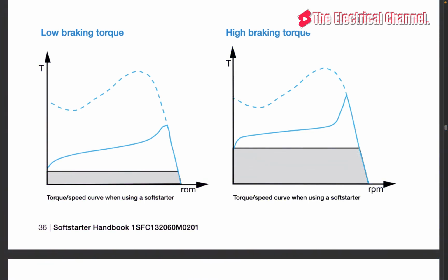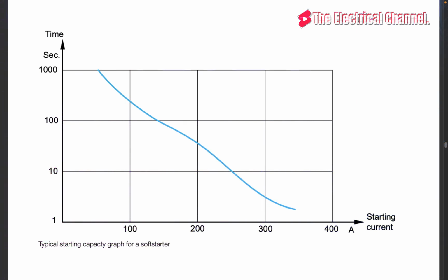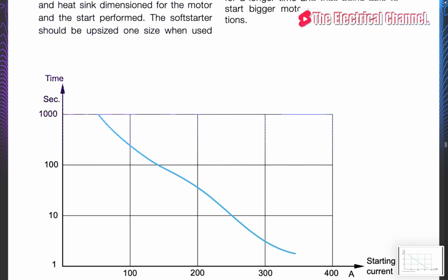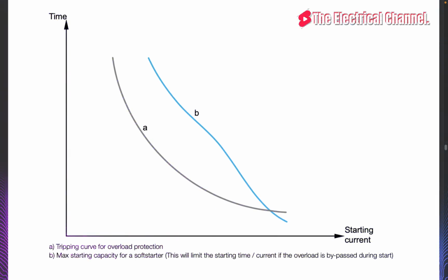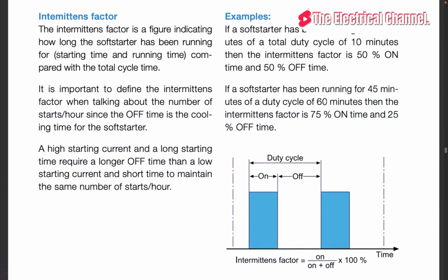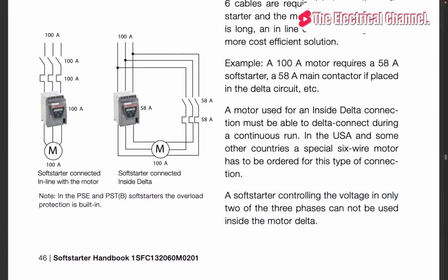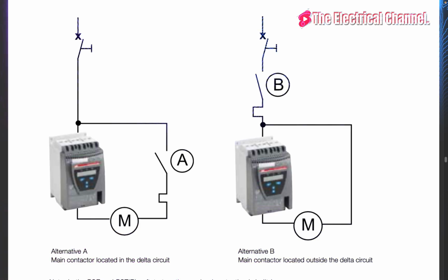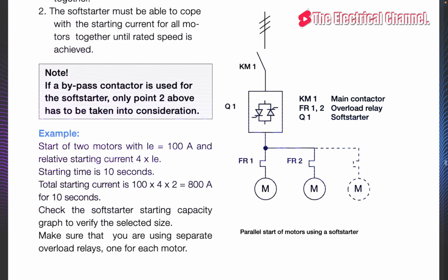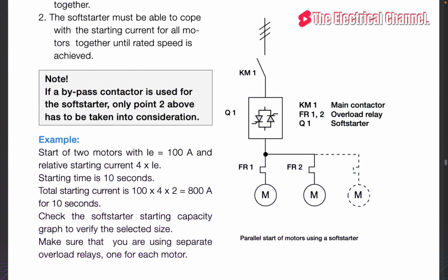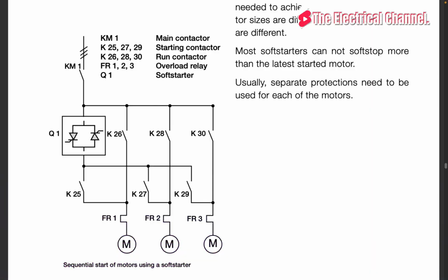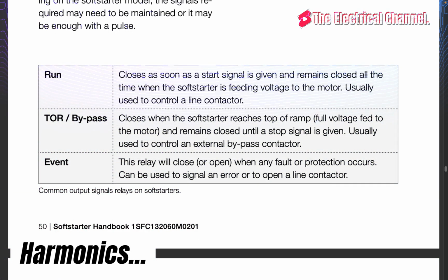Current limiting. Current limiting can be used in applications where a limited starting current is required, or at a heavy-duty start when it is difficult to achieve a perfect start with the setting of the initial voltage and the start ramp only. When the current limit is reached, the softstarter will temporarily stop increasing the voltage until the current drops below the set limit, and then continues ramping up the voltage. Since the maximum current, DOL current, is decreasing as the speed increases, the voltage can be gradually increased without exceeding the set current limit.